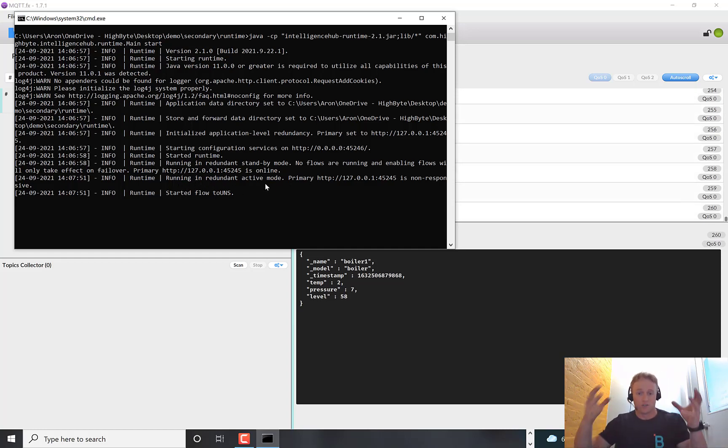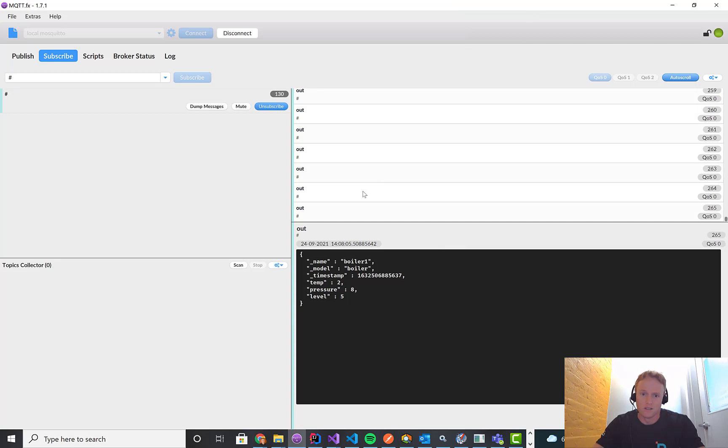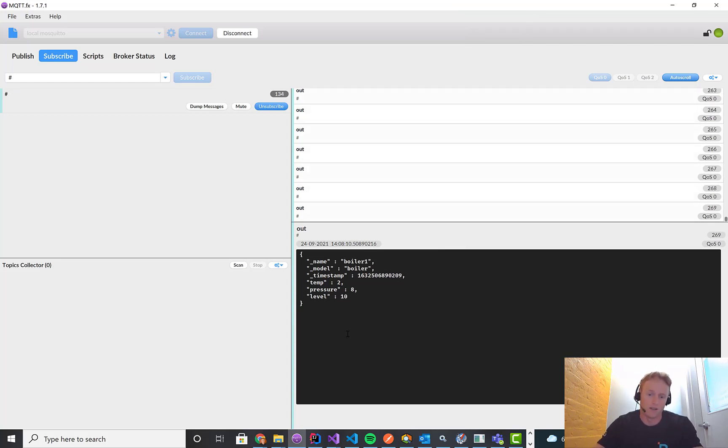And now it says running in redundant active mode. So now the secondary server has turned on because it hasn't gotten a response and it started up the flow. So now we can see the data is flowing again because the secondary server has kicked in because the primary went down.